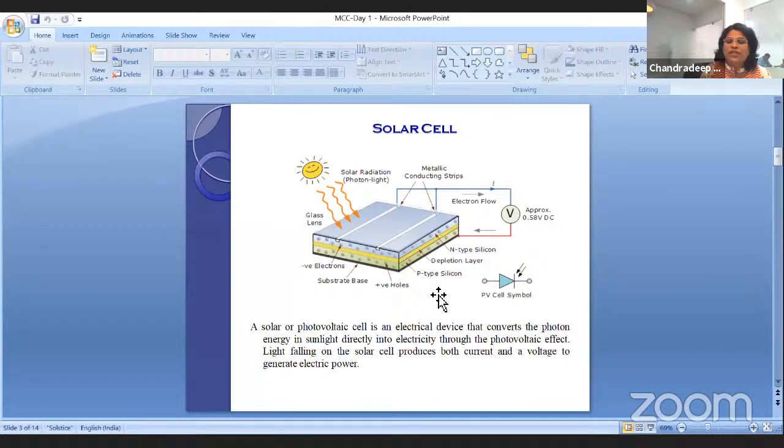Now, for the last 2 years, we are also taking into account the pollution level of the location. 2 years ago, we did not consider pollution as a main parameter in designing the power plant, but now we also consider pollution level in the design of the plant or water pump, because we have to install the solar module there. If the pollution is very high and it is deposited on the glass, then there is no generation of electricity. Most people have seen solar street lights installed in the main cities, but nobody is there to clean them, and they are totally dusty and the light is not glowing. It's only because the pollution is deposited on the glass. So the climatic parameters are most important before installing any solar application. If you are going for solar thermal, like water heaters, then you have to check the water quality of that location. So these things are needed.